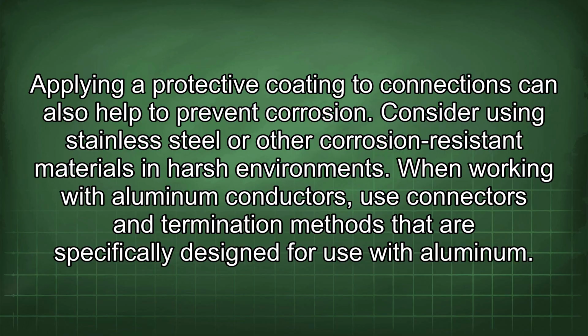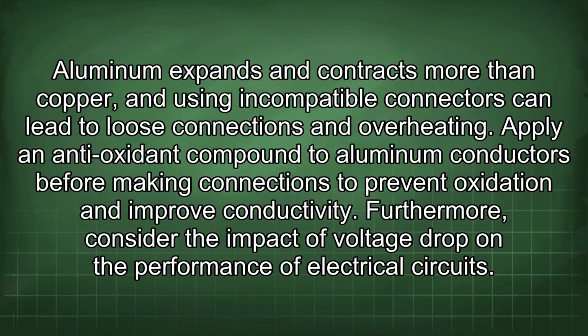When working with aluminum conductors, use connectors and termination methods that are specifically designed for use with aluminum. Aluminum expands and contracts more than copper, and using incompatible connectors can lead to loose connections and overheating. Apply an antioxidant compound to aluminum conductors before making connections to prevent oxidation and improve conductivity.